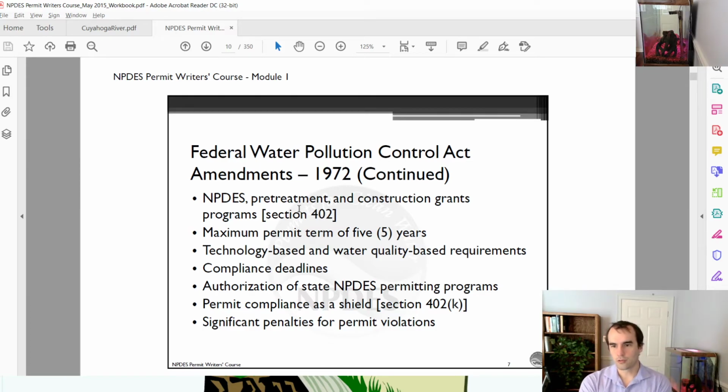Okay, so this led to the establishment of this NPDES system, with different programs associated with industrial pretreatment. If an industry is discharging to a municipal sewer plant, a wastewater treatment plant, then they might need some pretreatment in case you have some very aggressive chemicals in your industry, and then you send that down the sewer line, and all of a sudden you've killed that biological reactor. You killed all the biology in that biological reactor, and you have no more microbes doing the work. So maybe it was just a really intense pH shock that the industry sent down the pipes. That's a big problem. So there are certain pretreatment requirements so that the industry is not causing the municipal wastewater treatment plant to fail or to miss their effluent guidelines.